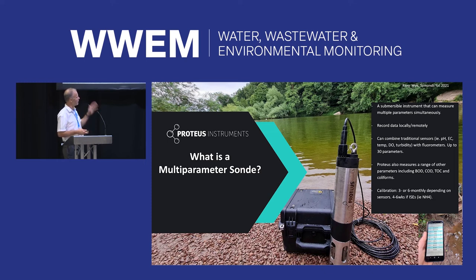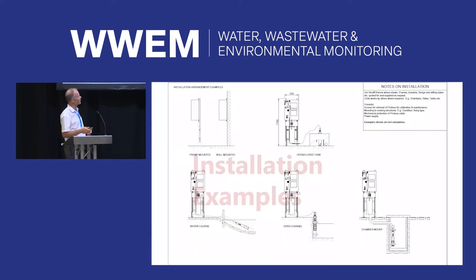Typically most parameters on our sondes will be calibrated every 3 or 6 months. Some are actually every 12, but there is one bad boy in the room, and that's ammonia. It's an ion selective electrode, and it needs maintaining or calibrating typically about once a month. There's no getting away from that, it's just what it is. So that's really a probe in a nutshell.